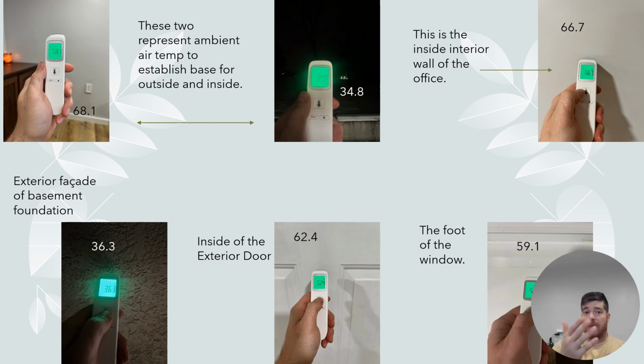Then the next is the foot of the window, which is 59.1, which is alarming because those are pretty bad, pretty drafty windows. But as you can see, this is wood on top of the 2x4 wall and also the CMU wall. So even with a 1-inch piece of insulation foam between them, they are still not retaining that thermal energy, and that's due to the inefficiency of the windows.